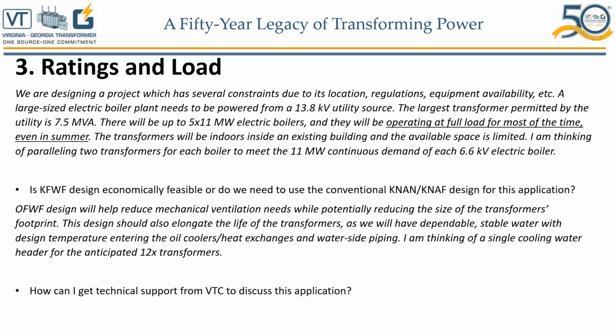Is KFWF design economically feasible, or do we need to use the conventional KNAN design for this application? So for those listeners here who may not know what KF and KN is, let me answer that real quickly. K, the first letter, stands for the insulating fluid. And when it is K, it is the insulating fluid with fire point over 300 degrees C. F stands for forced circulation through cooling equipment, such as cooling pumps, natural convection flow in the windings, non-directed flow. Okay, let's be careful, non-directed, because there is a follow-up question on this one about the directed flow, and I'll answer that. And then W stands for water, and then the last letter F stands for forced circulation, such as fans, pumps, water. So let's continue before I answer that question, because the answer to each question is one, okay?